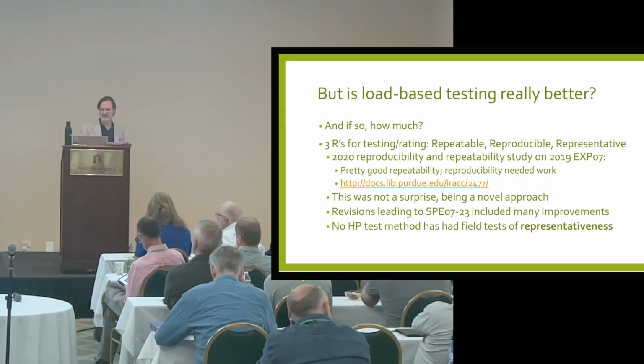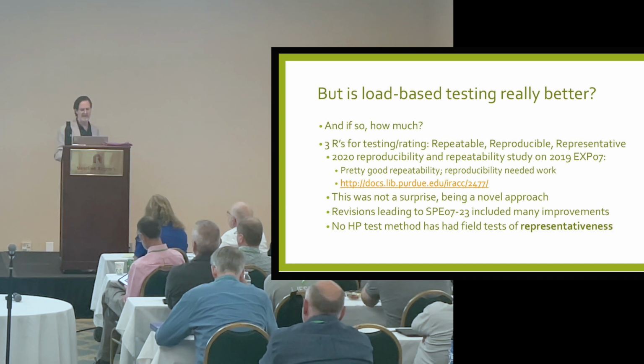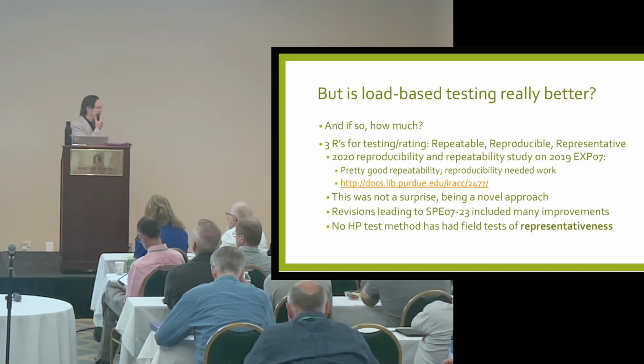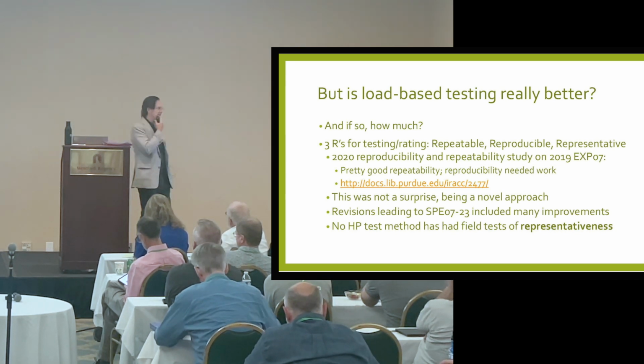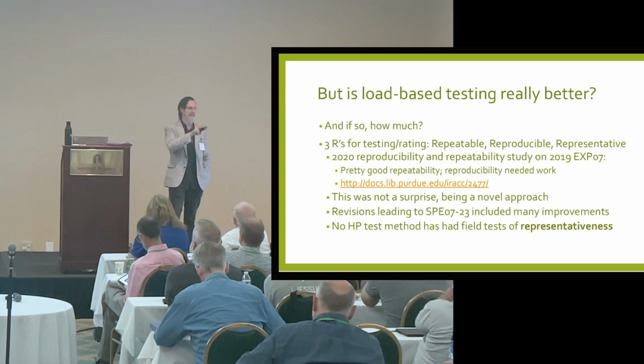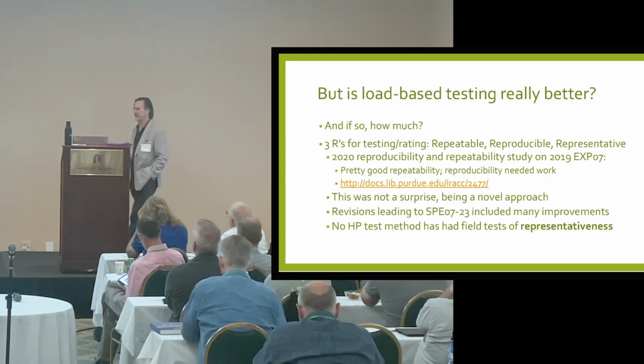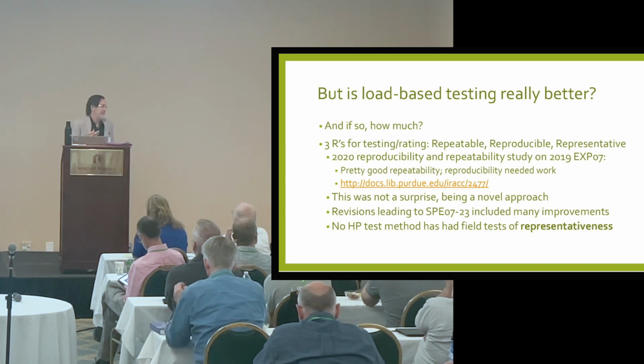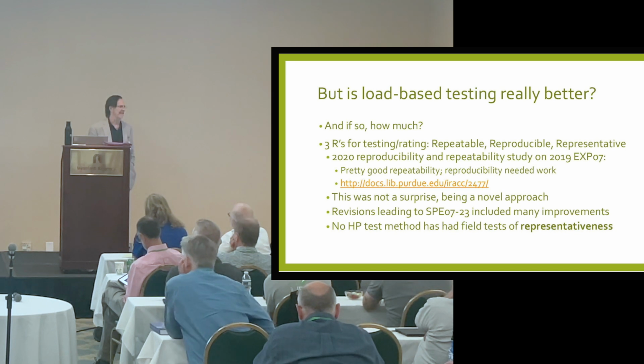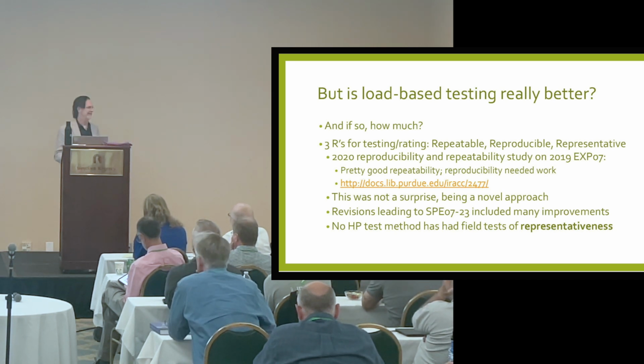Reproducibility was looked at and wasn't great with AHRI 1370. The repeatability was pretty good. The reproducibility wasn't really a surprise that it didn't do well, because we only had two labs that tested, I think, five different machines, and one of the labs wasn't really up to speed on the load-based testing. It's a novel approach, and lab people didn't all read the standard exactly the same way.